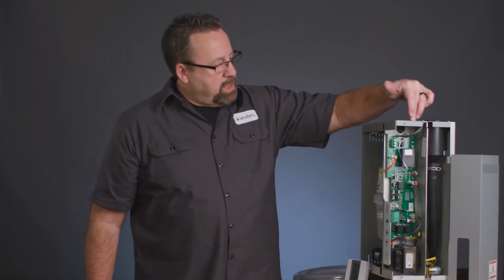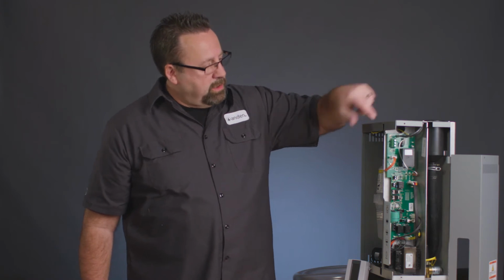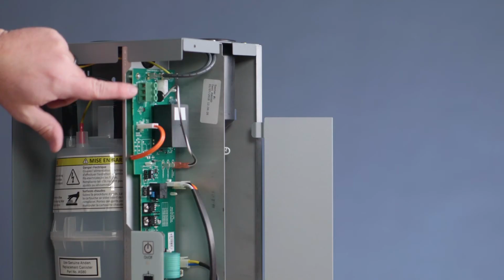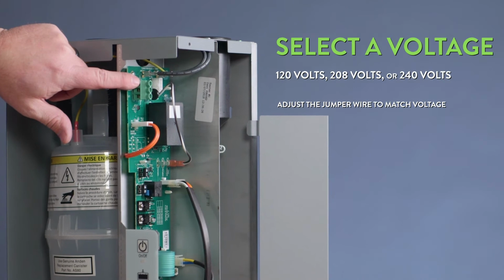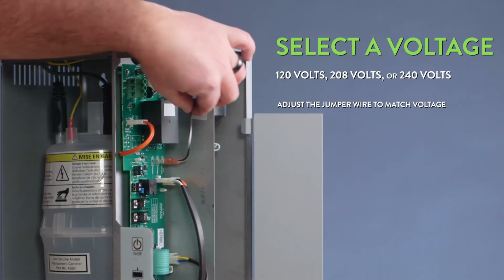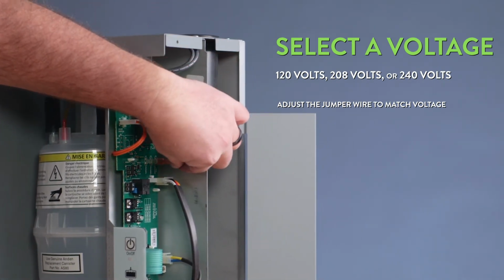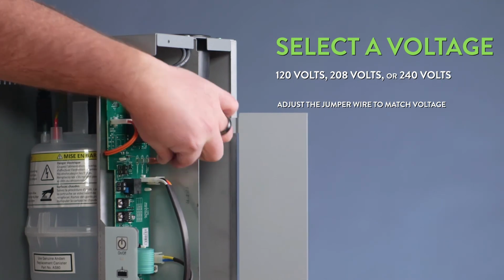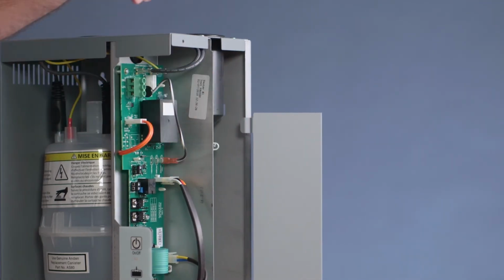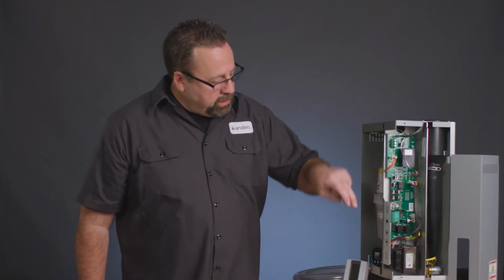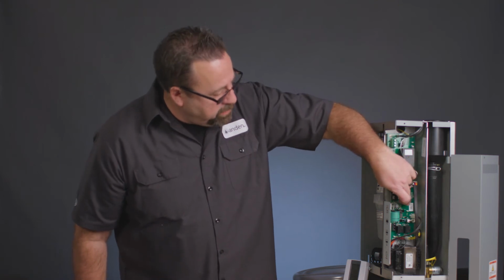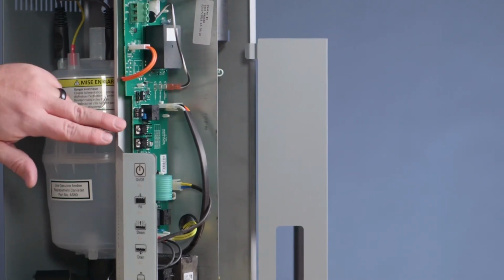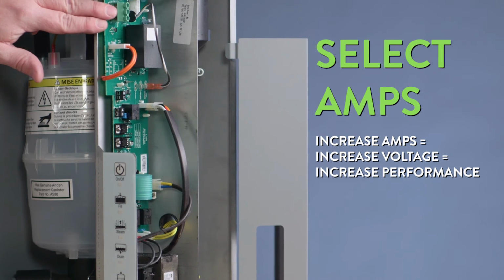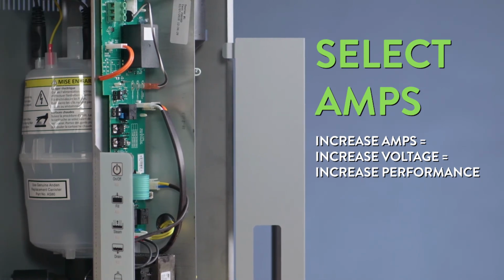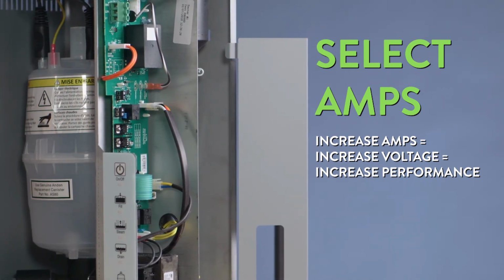Electricity comes in through the top, our high voltage electricity, right to these connectors here. The unit will run on 120, 208, or 240, and you simply move this jumper wire to whichever voltage you're applying to the unit. It's all matched up right there. One other thing to note, there is a bank of dip switches down at the bottom, and that's for the amp draw. The higher you set the amp draw, the higher the voltage that goes into the unit, the more output it'll have to get that 277 pints a day.